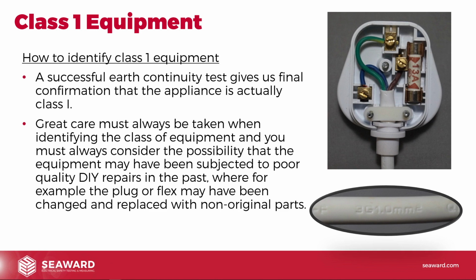I've also seen appliances where they've used 3-core cable, but they've cut the earth off because it was tripping. It's tripping the RCD because the equipment's faulty. Oh, that's a nuisance, let's cut the earth off to stop it tripping. And you might look at it and go, oh, actually, it's Class 2 equipment, that's fine, not check the earth and not carry out the correct insulation resistance test, and you end up passing equipment that's actually faulty. So always be aware when you're identifying equipment.